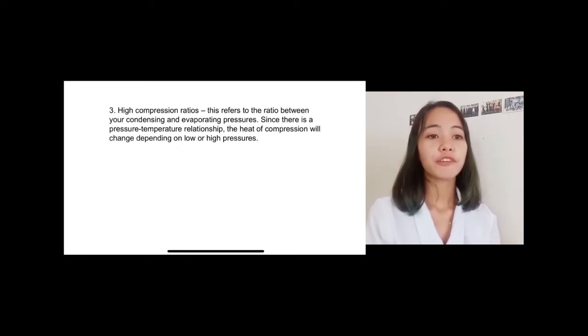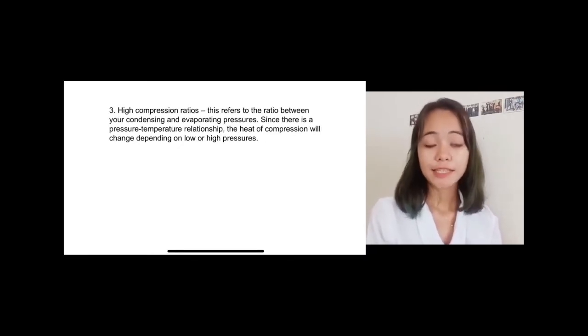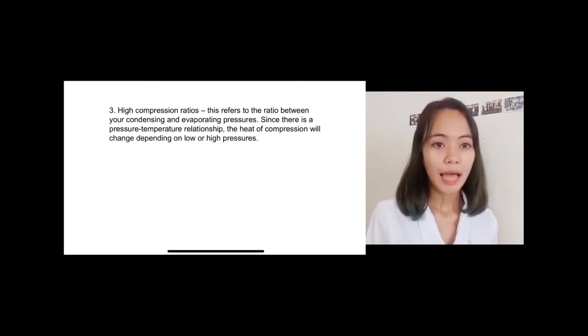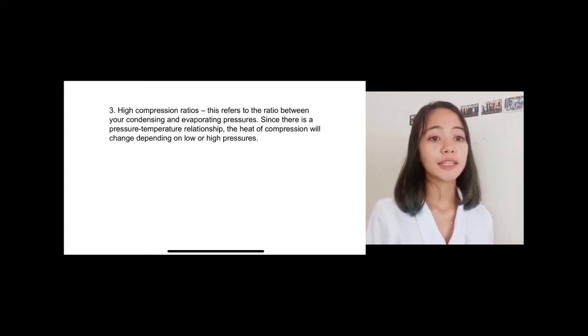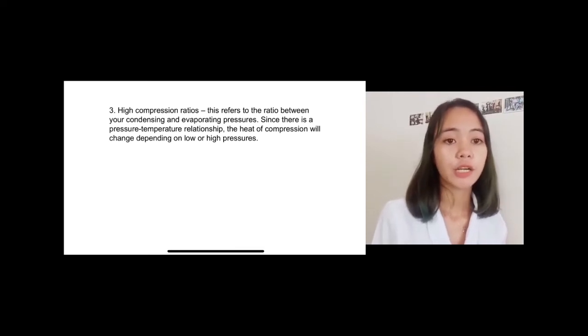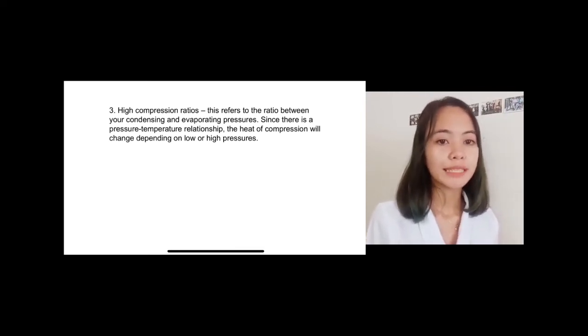The third would be the high compression ratio. This refers to the ratio between your condensing and evaporating pressures. Since there is a pressure-temperature relationship, the heat of compression will change depending on low and high pressures. If there is a high condensing and high evaporator pressure, the heat of compression will need to increase.